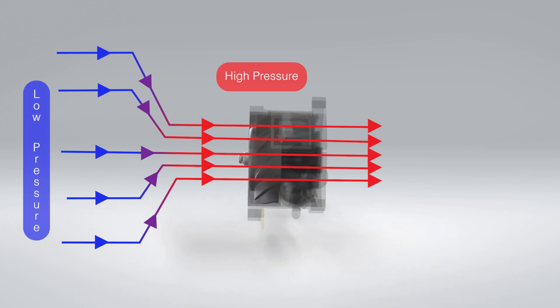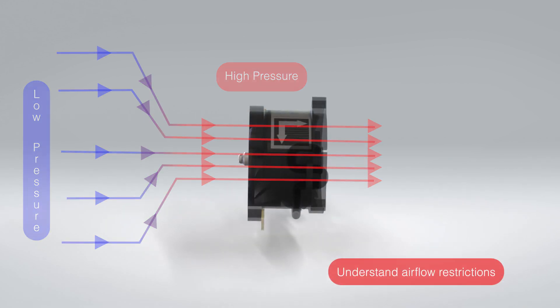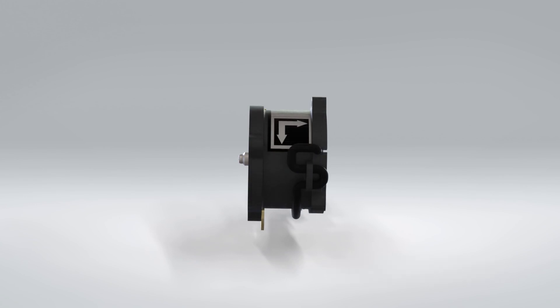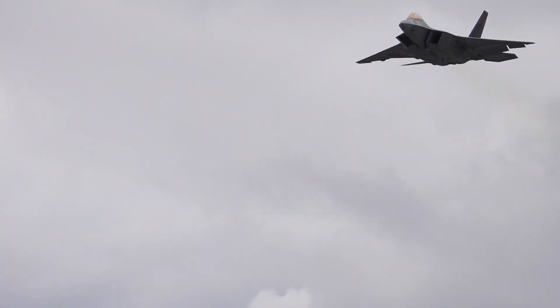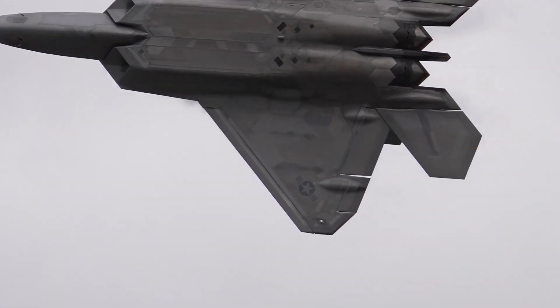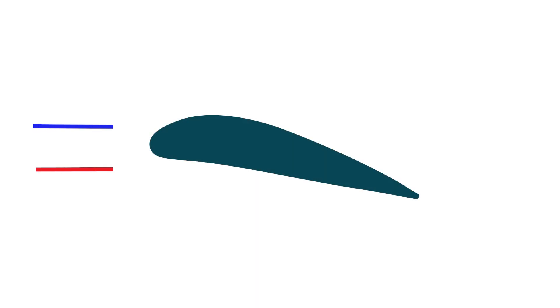It is, therefore, critical when selecting an axial fan to understand the airflow restrictions and not operate the fan at a point that will cause it to stall. An axial fan uses the same aerodynamic principles as an aeroplane wing, whose airfoil section generates lift, or airflow in the case of a fan.